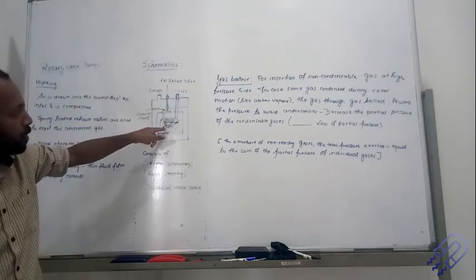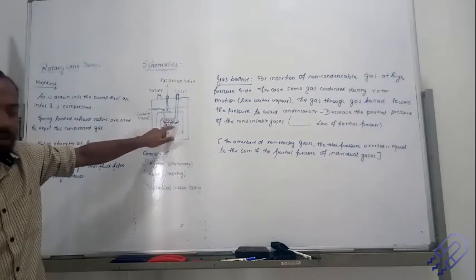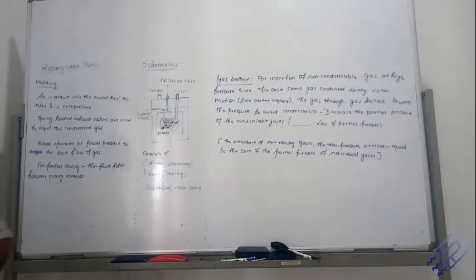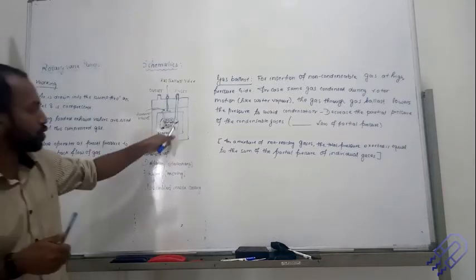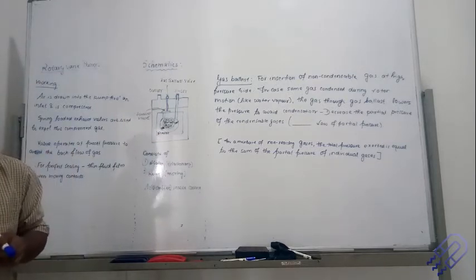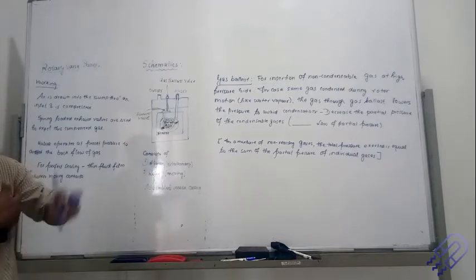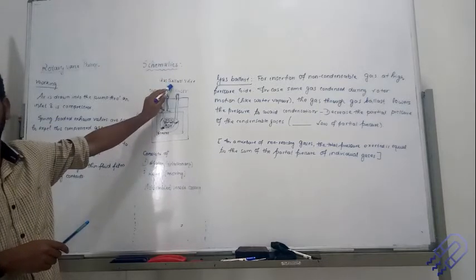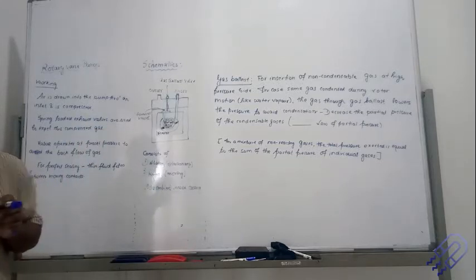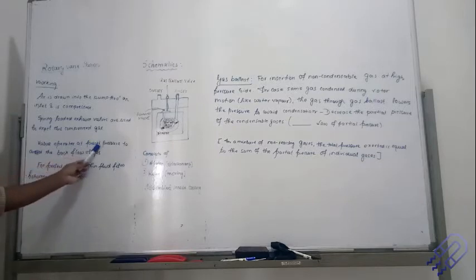When the rotor rotates, whatever air is trapped between the vanes gets compressed. Whenever there is compression, there is a chance of condensation because of the change in pressure — high pressure increases condensation chances. To avoid this, a non-condensable gas is introduced through a gas ballast valve, which modifies the pressure at which condensation occurs. The ballast valve operates at a preset pressure to avoid condensation of gas already present.